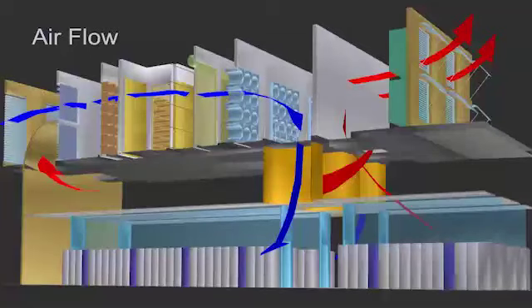We used fan array systems to pressurize the supply air plenum, pushing the air down into the data hall, treating the data hall as a large plenum space. So we just pressurize that space. The air would then go through the servers into the hot aisle containment, up into the plenum. Depending on the time of year and the conditions outside, we'd either purge that waste heat or recirculate it back into the building and do our mixing.